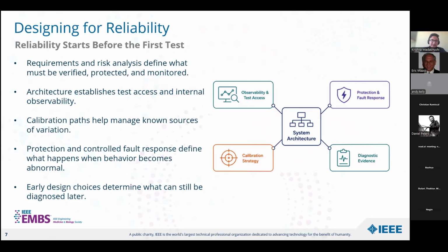That includes designing for conditions outside our normal operation. The device may encounter a sudden electrical transient, a clinical interference like an MRI event, or an extreme temperature change. The response to these conditions cannot be improvised after the product is built. It has to be designed when the system is built and then verified.